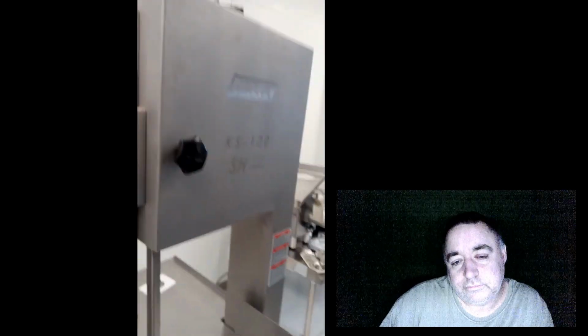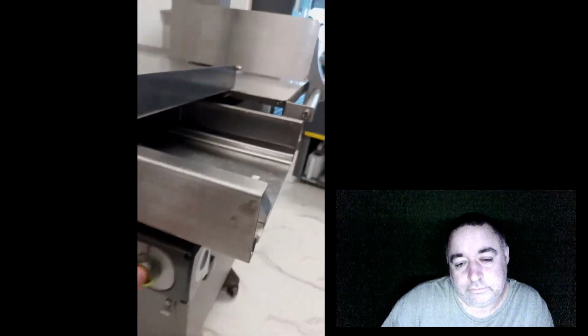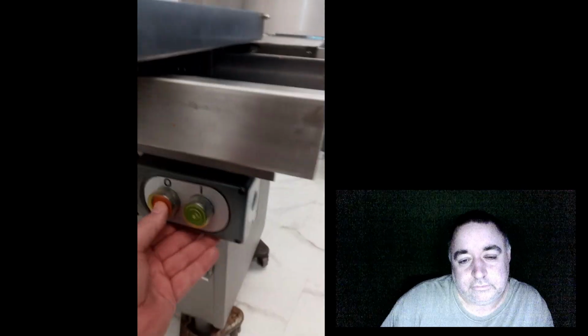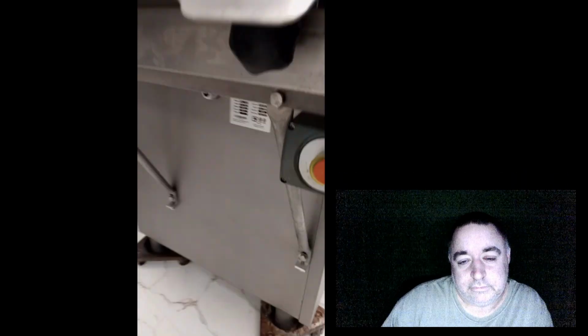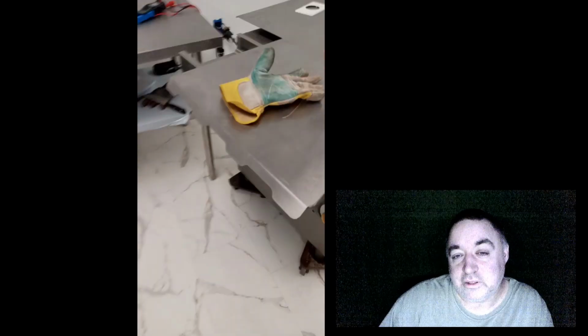Lockout switch. Off, on. Emergency switch. Off, on. Master switch. Nothing. It's the machine, man. It's got to be. I got full power coming out of that wall now. Well, that breaker was very loose, though. But watch what I find next. This is interesting. Check to make sure I got power on all 3 phases, and I just come across something else. Look at this. Check this out.